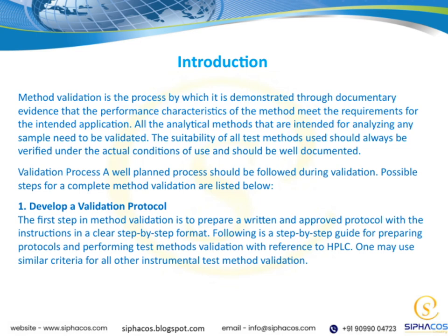For example, when validating an HPLC method, you'd create a protocol that specifies all the parameters, conditions, and acceptance criteria. The good news is, the same principles generally apply across different instrumental test methods. So once you master preparing these protocols for one technique, it becomes easier to adapt them for others. In summary, developing a solid validation protocol is foundational. It guides the entire process and ensures that our method validation is thorough, consistent, and aligned with regulatory expectations.